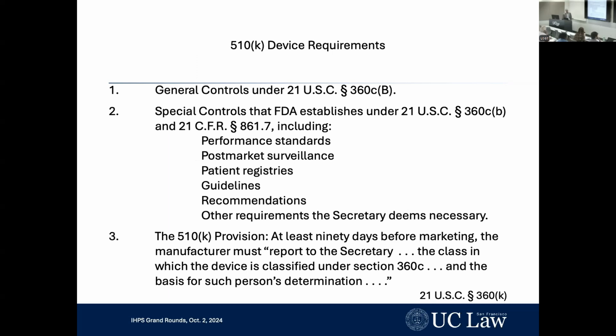Well, first, the manufacturer has to follow any general controls that the FDA has. So if the FDA writes up a list of good manufacturing processes, which could be anything as simple as good electrical grounding in your factory, all the way through more complicated things, the manufacturer has to follow those. Those apply to all devices. Then there are special controls, so the FDA can identify a particular generic kind of device, let's say a metal-on-metal hip prosthesis, and it can establish certain requirements for those. It can set up a performance standard, like that the device has to be able to support so much weight, or it has to be able to bend and flex so many 100,000 times, or it's got to be coated with specific biocompatible materials, right? The manufacturer has to comply with those.